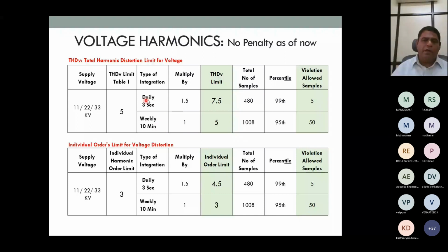For a 3 second integration, the standard gives a multiplication value of 1.5. That is 5 into 1.5 is equal to 7.5. So there is a big relaxation in this. We can go up to 7.5% for a daily 3 second value, is what the standard says. So when it is a 3 second value, there will be 480 samples per day.